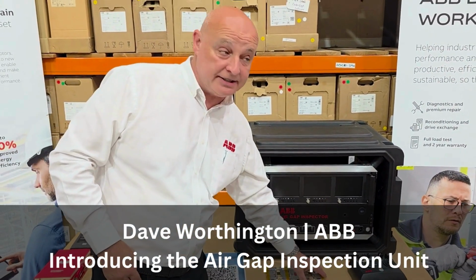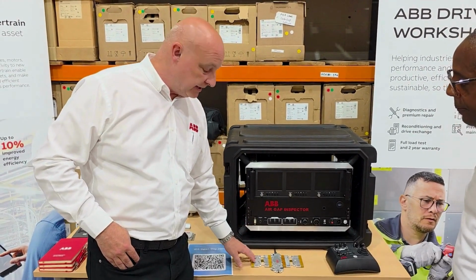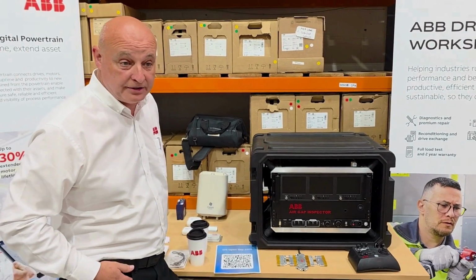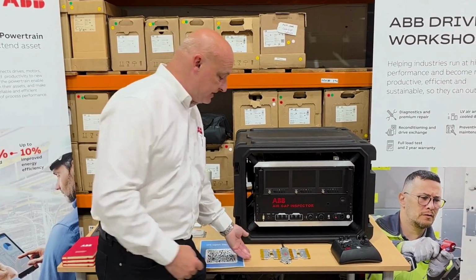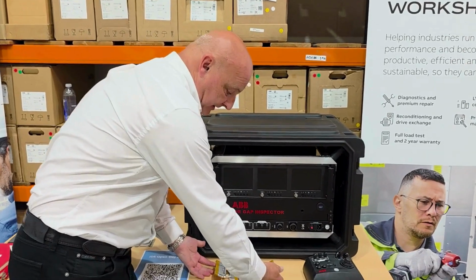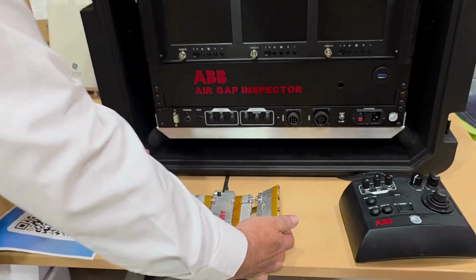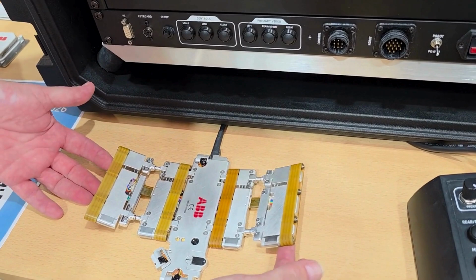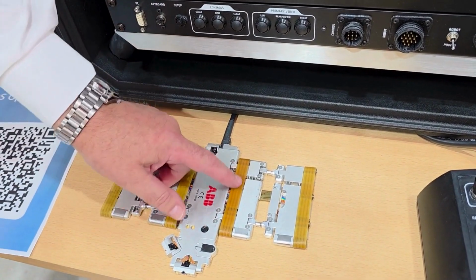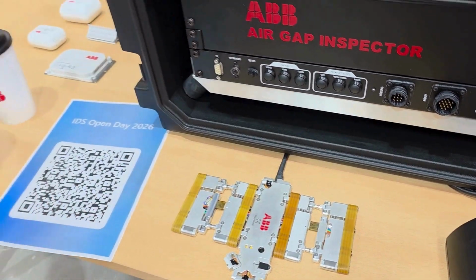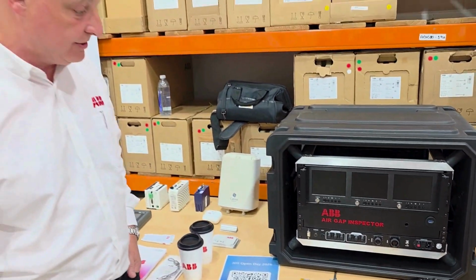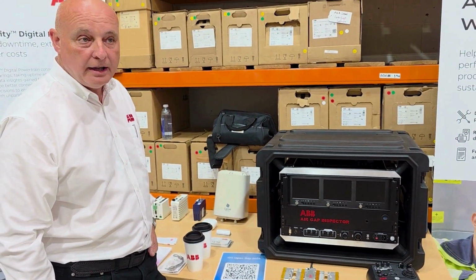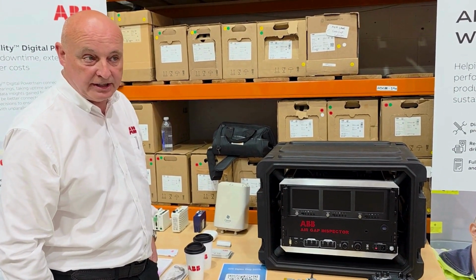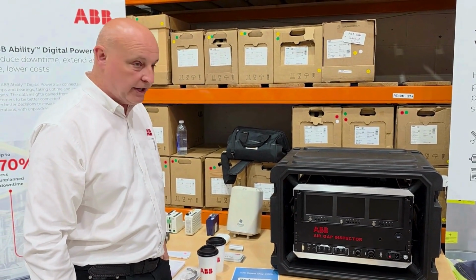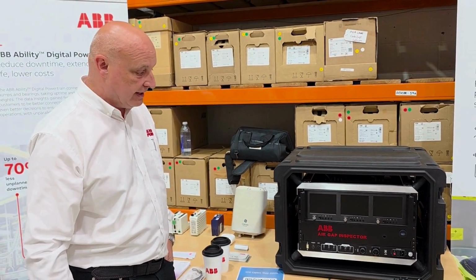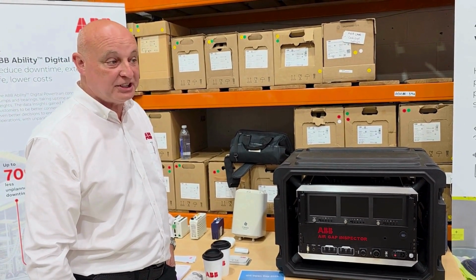This is one of the services we offer. Any large generator machine that has an air gap between the stator and the rotor of more than 12 millimeters, we can put this camera down, which takes up the profile of the stator. These tracks allow the device to go up and down the full length of the core, so we can examine the internal condition of the generator windings and rotor without having to remove the rotor, which is a very risky procedure.